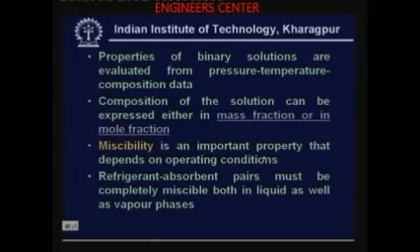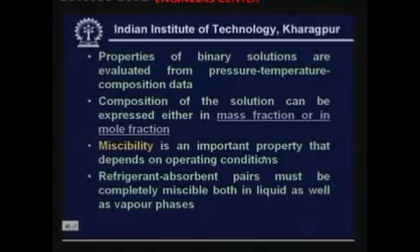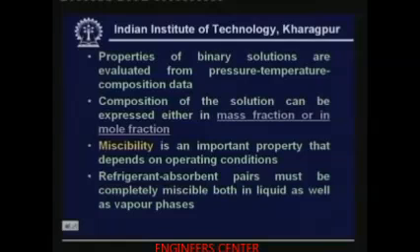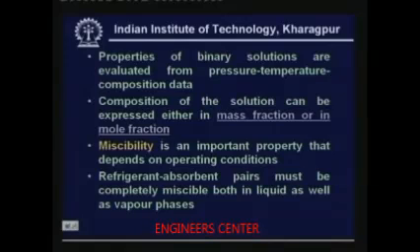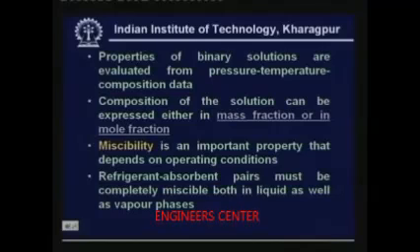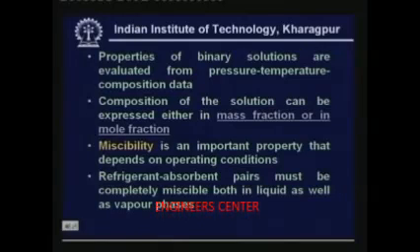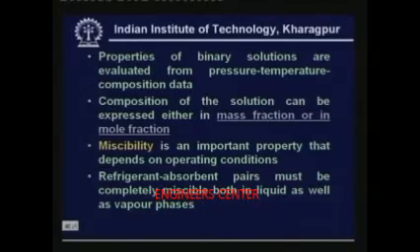Another very important property for refrigerant-absorbent pairs is miscibility. Miscibility depends upon the operating conditions — under certain conditions a refrigerant-absorbent pair may not be highly miscible, whereas at other conditions they may be highly miscible. Generally, refrigerant-absorbent pairs must be completely miscible both in liquid as well as vapor phases, so that they get mixed completely and you get a homogeneous mixture.